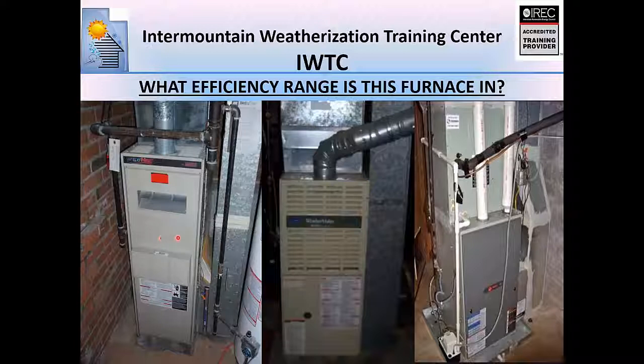Also take note of the louvered front doors, okay? Anything less than 90%, so like this guy over here is an 80%, and notice the big hole in the door is gone, but we still have a louvered door. Anything less than 90% will have some kind of louvered door on it to allow combustion air to get into the burners. And then of course over here we have a 90%. The quickest way to tell is the flues. Anything that's 90% efficient or higher is going to have typically some kind of plastic flue because the flue temperatures are so low. Everything else is going to have some kind of metal flue.